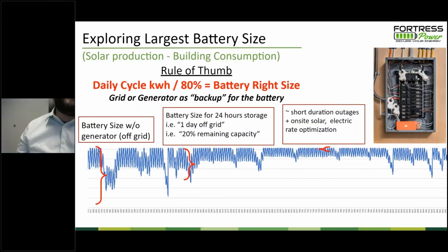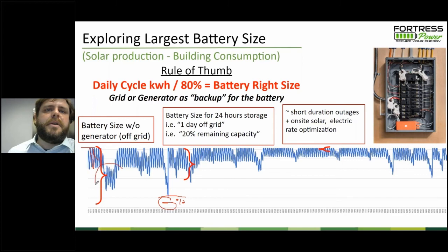But what I wanted to point out with this slide in particular is, there's a couple of different approaches to battery sizing, and the first is to say, okay, you want to have this 20% reserve capacity. And so if you start at 120 kilowatt hours and you're subtracting out your day-to-day load and adding back in your day-to-day production, ultimately you're going to get into a period where the sun doesn't come back up. And so for off-grid without a generator, you'd plot out your entire PV Watts data for the whole year. You'd subtract your consumption data for the whole year, and you'd look at that minimal amount and say, okay, I want to have 20% left in the tank, and that's my good battery size.